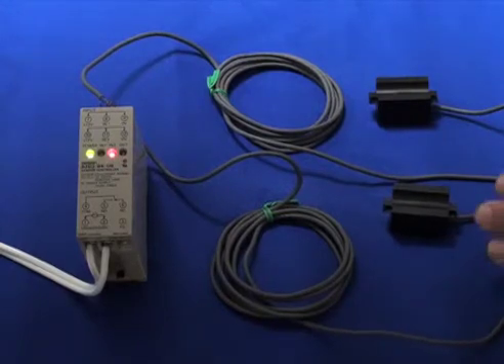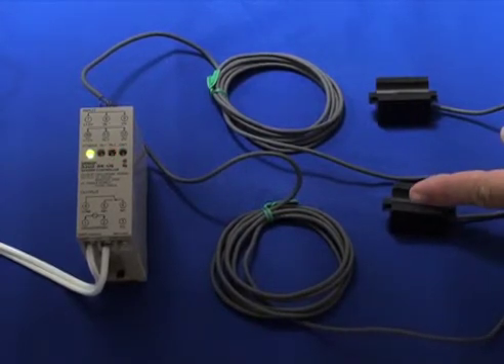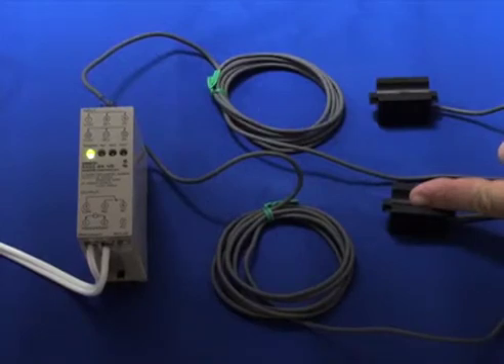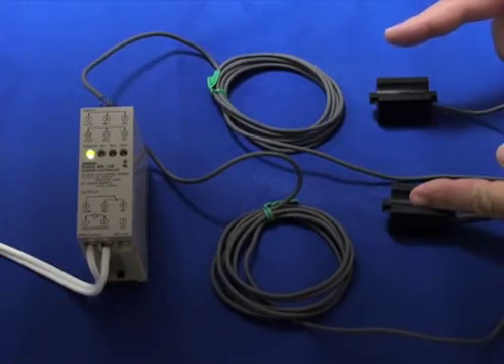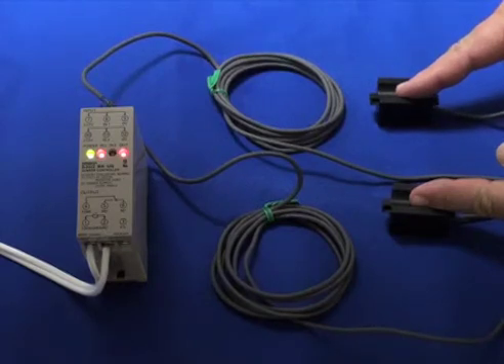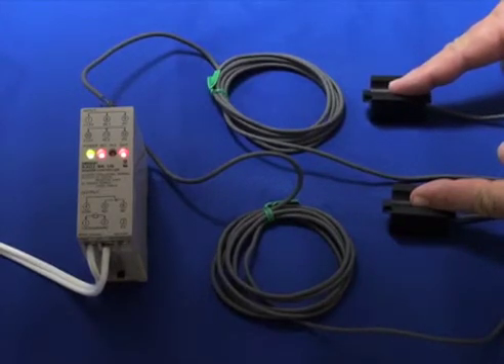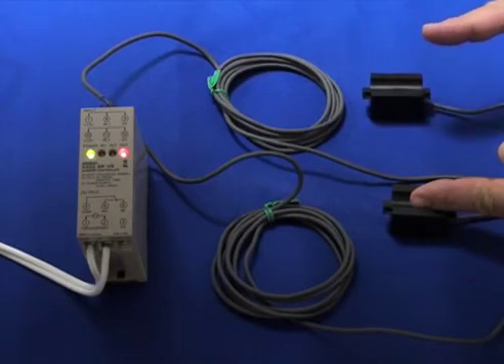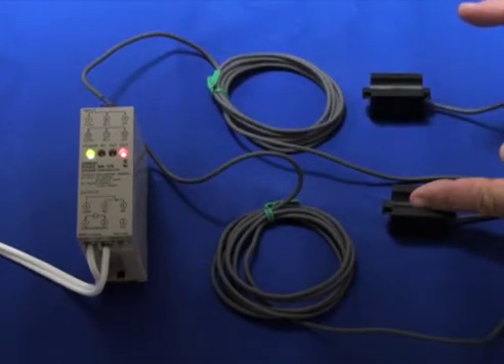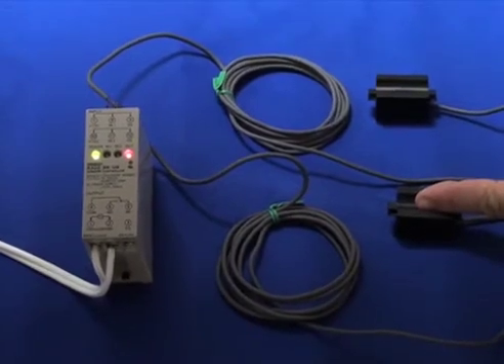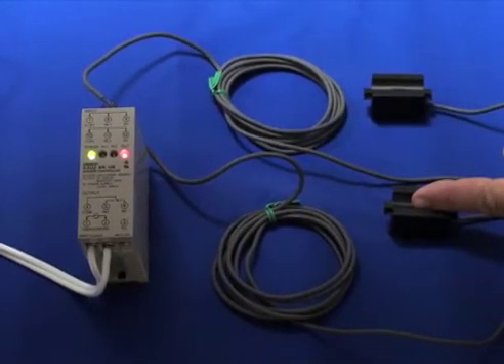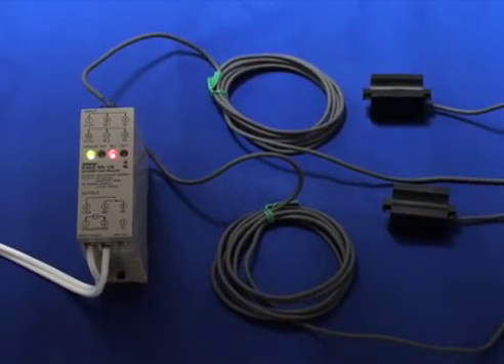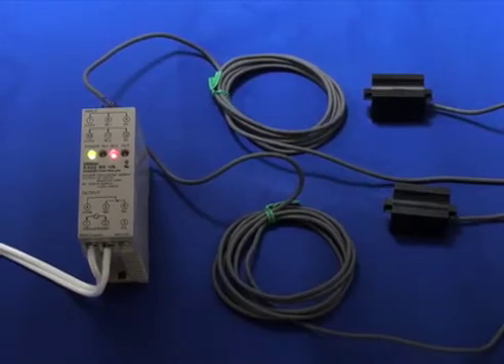I can say it again: water comes in, it hits the low level sensor and turns off, it continues to fill until the high level sensor makes and turns on a pump. The pump pumps out the wastewater, the water level starts to go down, the high level sensor turns off, and the pump stays on until the water falls below the low level sensor and then the pump resets. And there's your application.